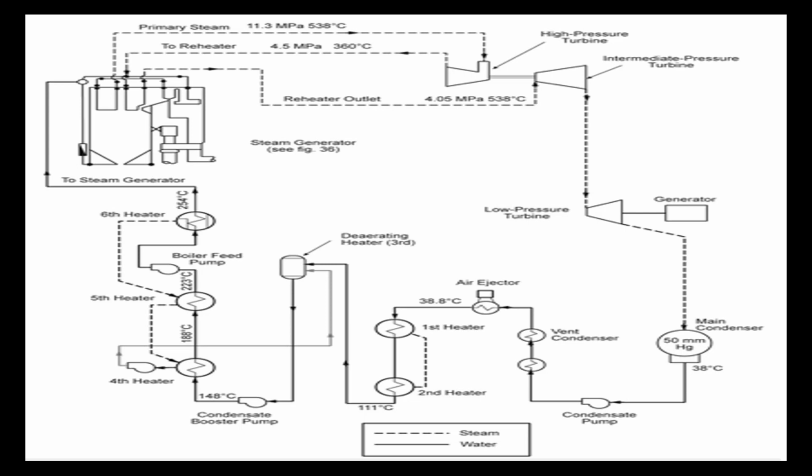Now on the downstream side of the boiler feed water pump, they are high pressure feed water heaters. These are simply usually regenerative feed water heaters that are going to be basically heating up that feed water in gradual steps to get closer and closer to the saturation temperature that's occurring in the steam boiler. From here, after it passes out of our last feed water heater, it will then pass into the economizer and away we go through the boiler.